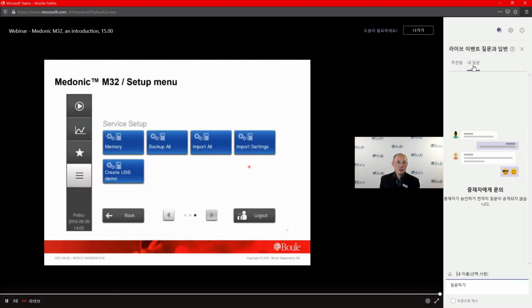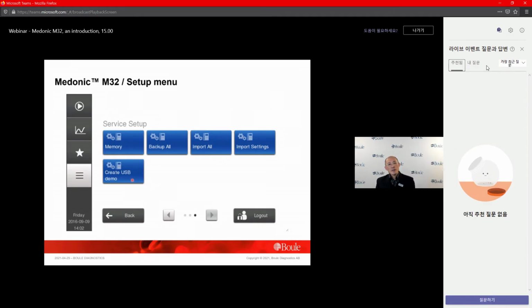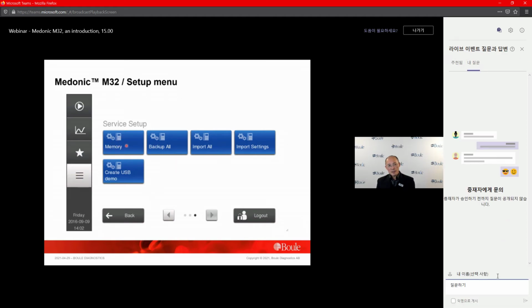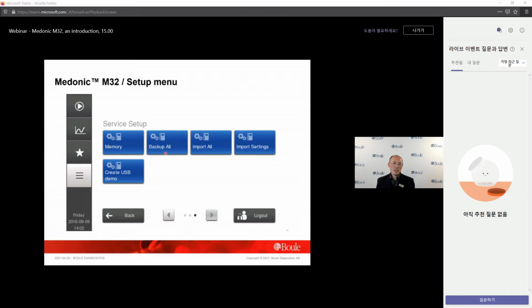The service setup provides a function for the memory setting, where the raw data can be saved, mainly for troubleshooting to get more low-level data. And here, backup, import, and setting can be used to save a setting from one instrument and then give a group of other instruments a similar setting, for large labs or a chain of clinics. Create USB demo is to make a USB demo disk, and on another instrument start a demo without running reagent on that instrument.